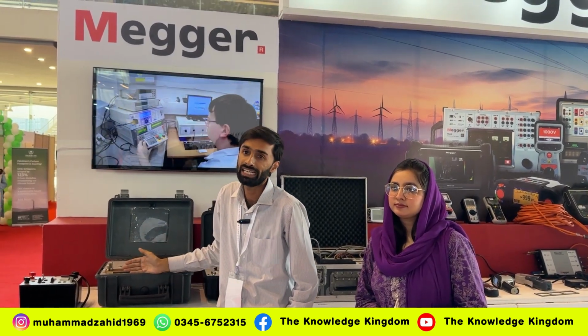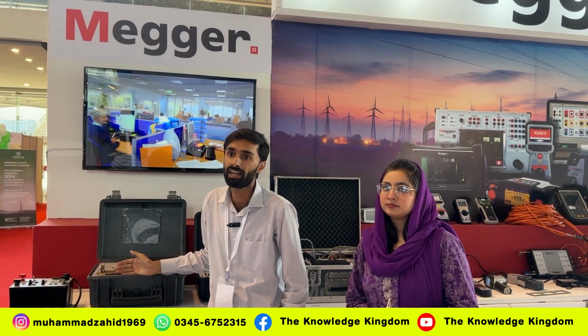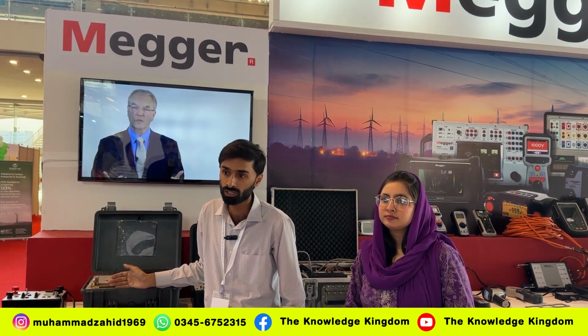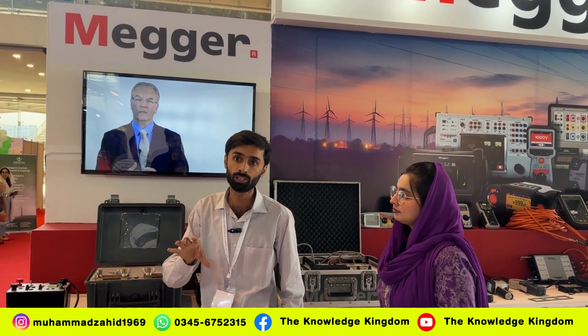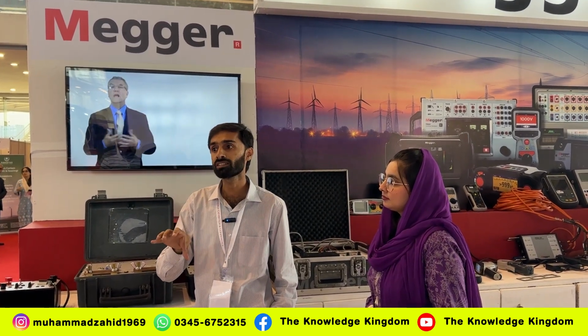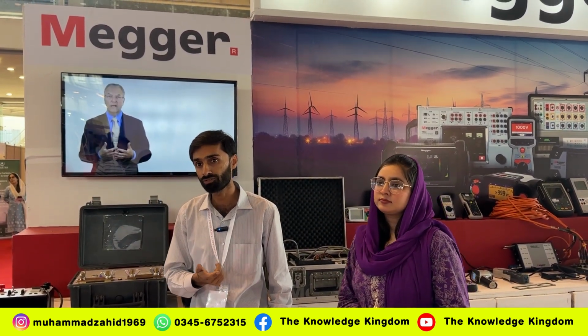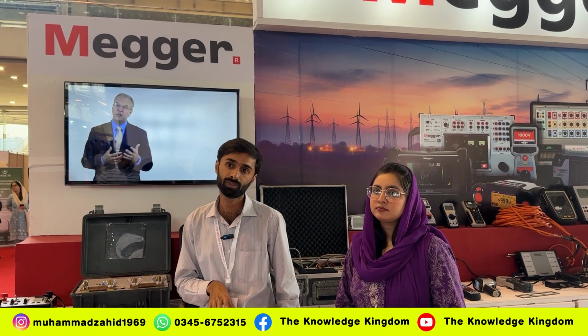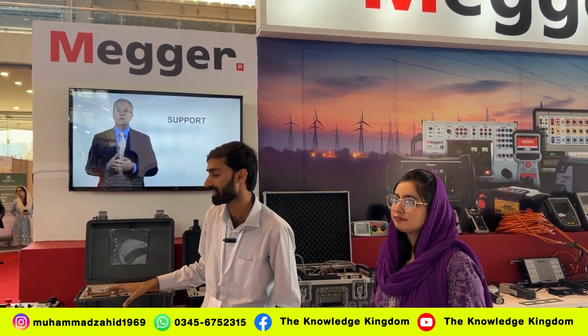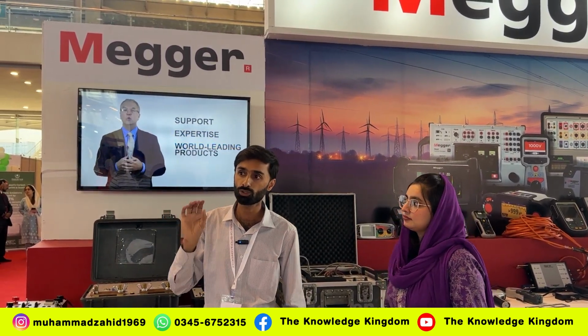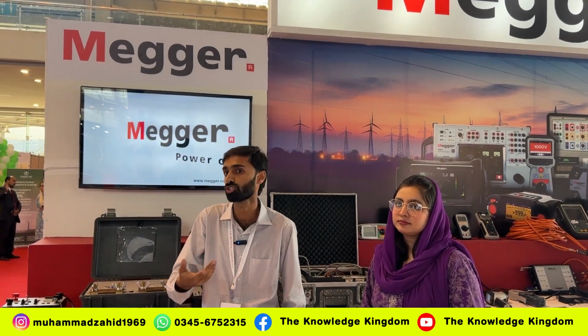Plus you have the ACBs which operate at thousands of amperes at the fault. You can give that fault current to your ACB in order to check that when the fault current actually travels, will it trip or not? And you check the trip time. So basically that is the application. The application is in the sugar sector, again the utility sector and the substation system.